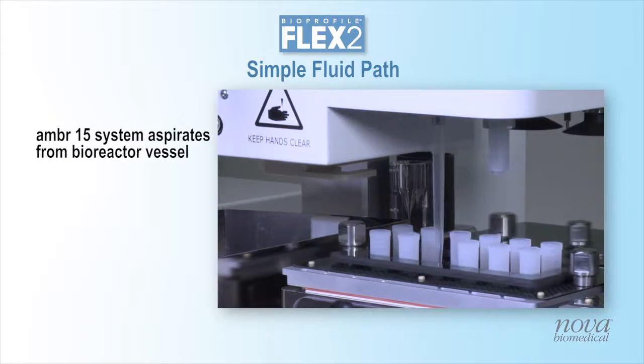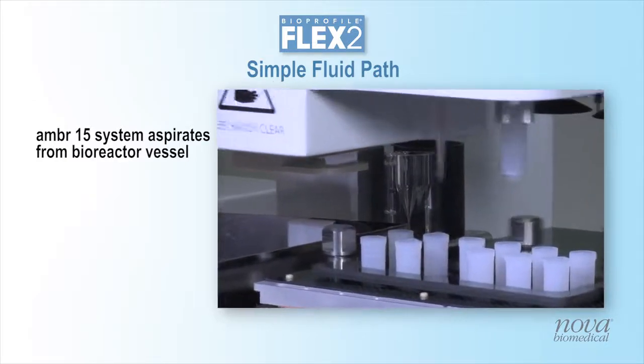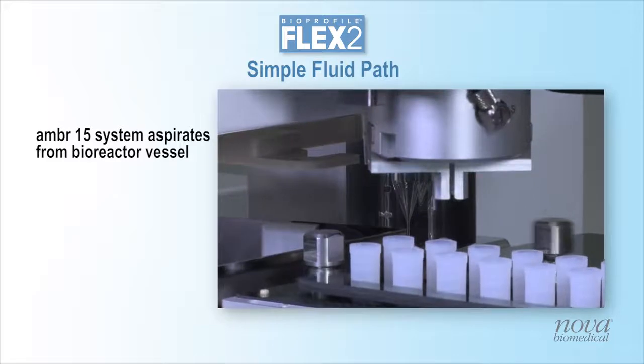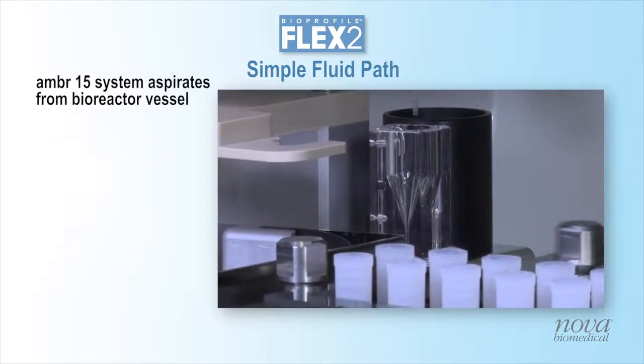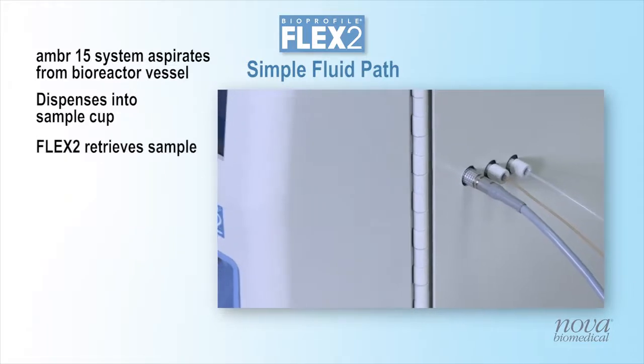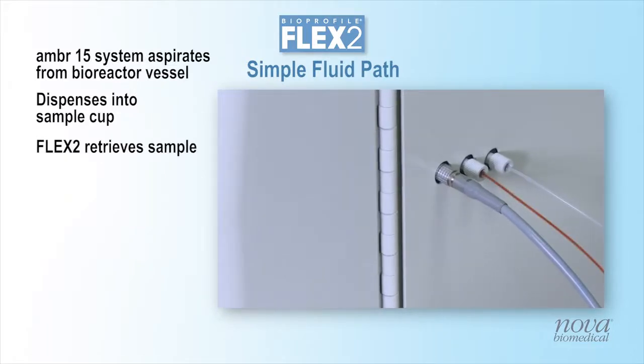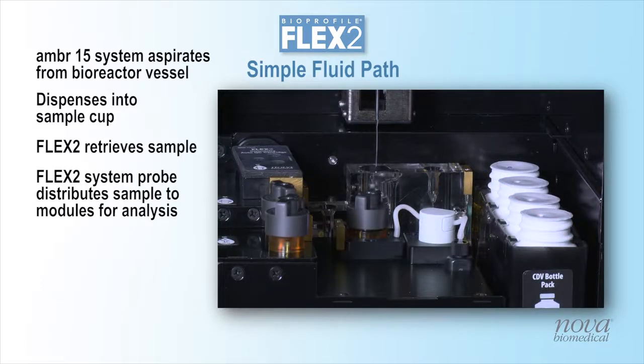When scheduled, a sample is aspirated from an AMBER micro-bioreactor and dispensed into the custom acrylic cup on the AMBER deck. Flex2 retrieves the sample from the cup for analysis. The Flex2 system probe distributes the sample to the appropriate modules for analysis.